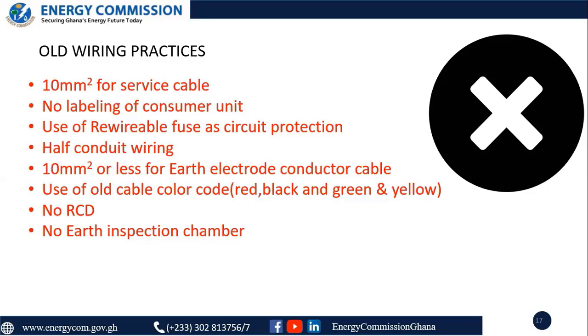Then a 10 millimeter square or less for earth electrode conductor cable. That is also out of the system. You ask the electrician, what cable gauge are you using for my earthing conductor cable? And once he says 16, then you are good to go, because you've confirmed that he's using 16.